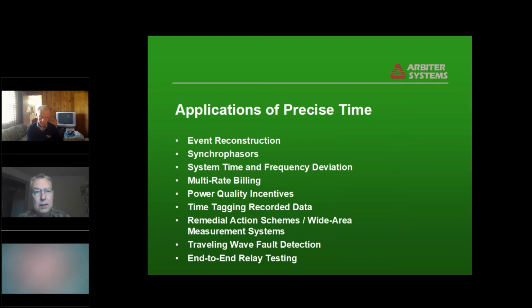The 60 hertz power grid signal in North America and many other places is used as a time reference to run wall clocks and things like that. So the utilities use precise time to keep the average frequency adjusted for that purpose. Multi-rate billing, you're probably familiar with the fact that utilities charge different rates at different times of the day. There are power quality incentives, the same sort of thing, that it's important in different times of the day. There are greater concerns and issues than others. General time tagging of recorded data.